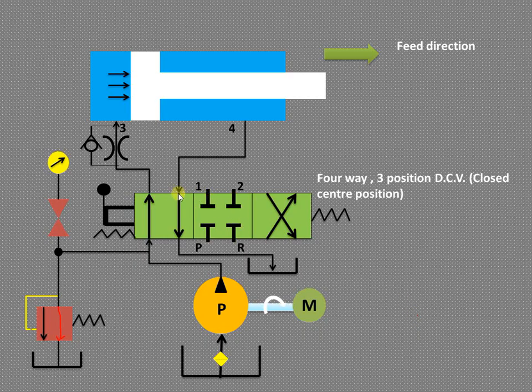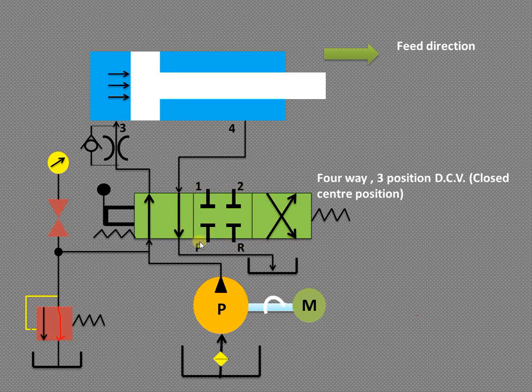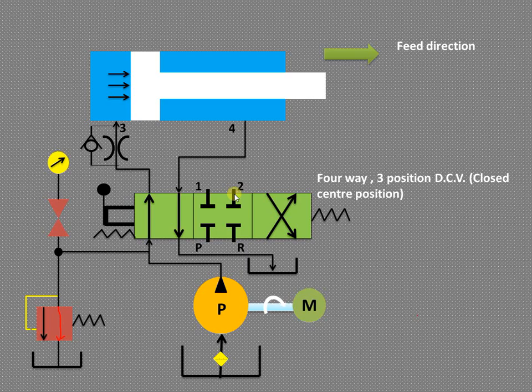Now this is the most important part of any hydraulic circuit. Here we have shown four ways: P, R, 1, and 2. P stands for the pump port, R for the receiver port, port 1 is the inlet to the cylinder, and port 2 is the outlet from the cylinder or vice versa. This is the center position and it is a block position.